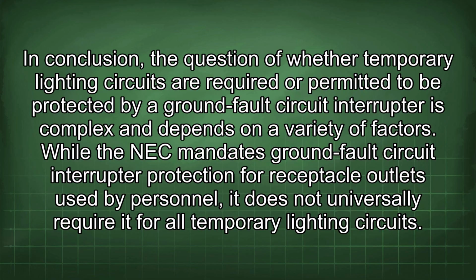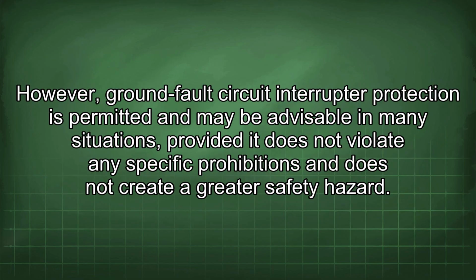In conclusion, the question of whether temporary lighting circuits are required or permitted to be protected by a ground fault circuit interrupter is complex and depends on a variety of factors. While the NEC mandates ground fault circuit interrupter protection for receptacle outlets used by personnel, it does not universally require it for all temporary lighting circuits. However, ground fault circuit interrupter protection is permitted and may be advisable in many situations, provided it does not violate any specific prohibitions and does not create a greater safety hazard.